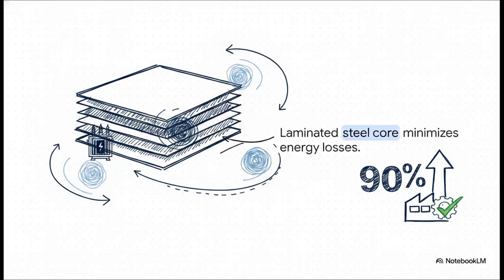Now check out the core that actually holds these windings. Notice it's not just some solid, heavy block of iron. No, it's carefully built out of laminated silicon steel. Why do it this way? Because it kills off what we call eddy current losses by up to 90%. That changing magnetic flux passes right through this laminated core, which makes our plant operations ultra-efficient.